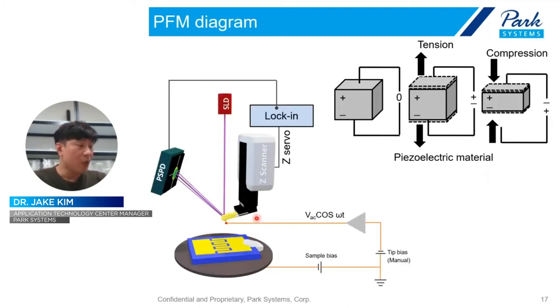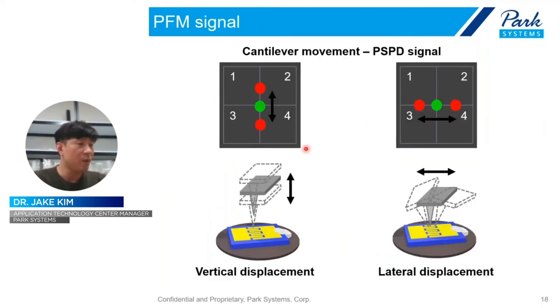So we recommend this conductive diamond or hard conductive material coated tip. Briefly, this one is a simple diagram of PFM. Briefly, the AFM tip contacts the sample and we apply the bias, then if the sample has a piezoelectric property, we can monitor this PFM signal. Like this, we can investigate the vertical and lateral displacement of the piezo sample and make an image of piezo signal contrast.